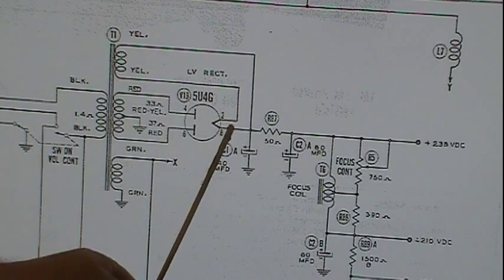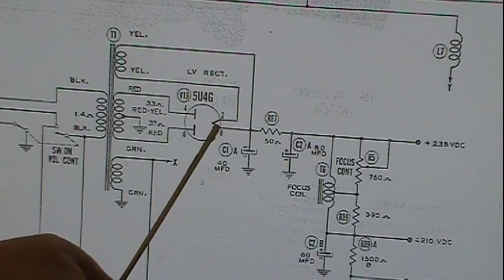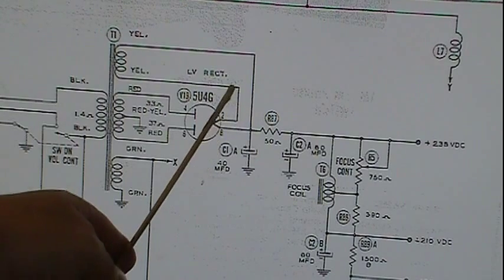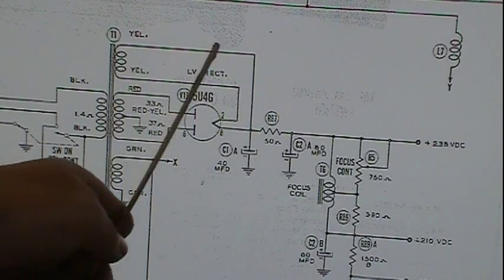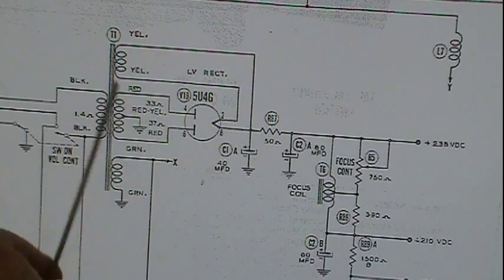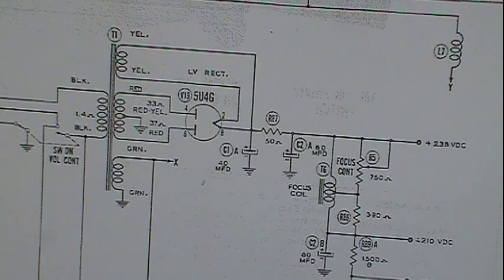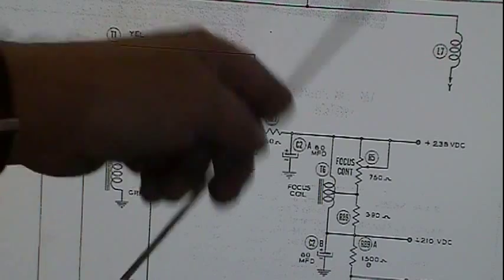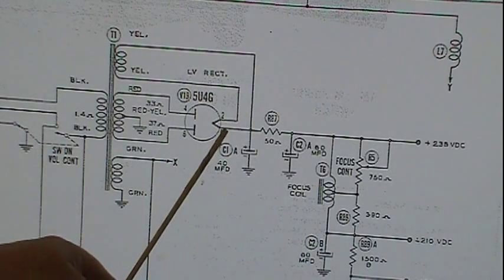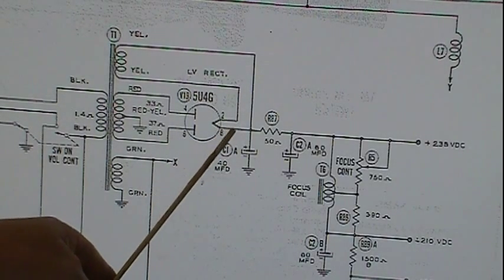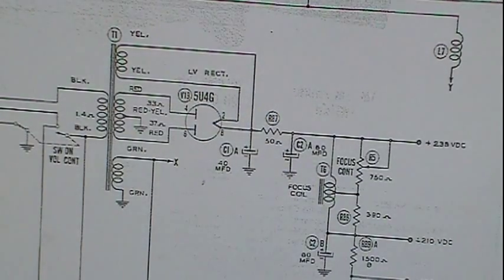Now that 240 volts is on pin 8, it's also on pin 2, through this winding, and back. It just makes a little loop. It does nothing. There's no path, no connection for it. It's just going around in circles. The only place that 240 volts can go is out this way.